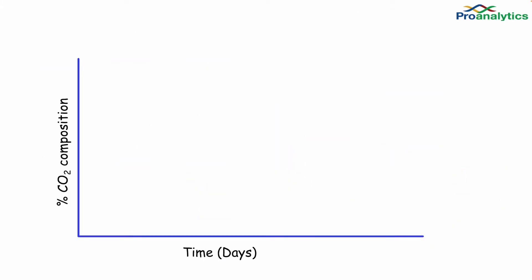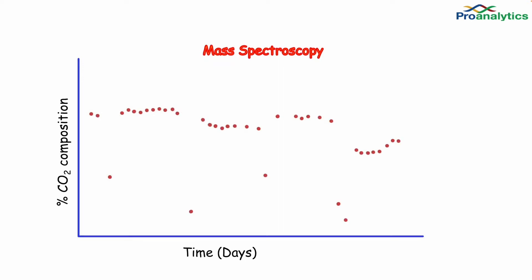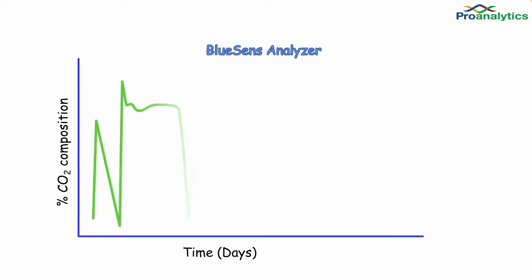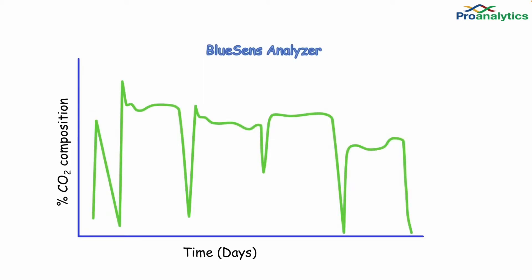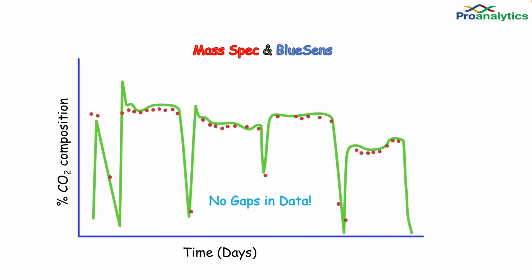Let's compare the data sets. Here we have the mass spectroscopy data showing all the sampling points in a run, and here is the BlueSens data on the same run. When we compare the two graphs, we can see all the data points that were missed by mass spectroscopy. The mass spec can be used to verify readings instead of trying to generate a point-by-point graph, and the ability to read data in real-time means there are no gaps in the data from run to run.